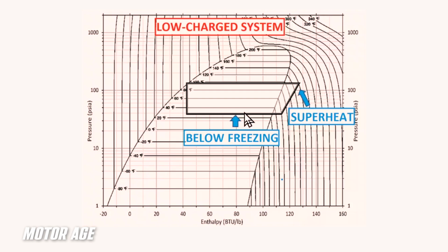So temperature is below freezing at this point in time entering the evaporator, and it's changing states from a liquid to a gas. And because the heat in the cabin has to enter or transfer into only a minor amount of refrigerant, it takes on more heat load, and this is where superheat takes place. So as you can see, the temperature as the refrigerant enters the compressor is increased. As the compressor outputs the compressed refrigerant, we are far into this superheat territory. So that means that the system, as we shed heat from the refrigerant across the condenser to the air, has to shed more heat energy before it can convert from a gas back to a liquid.